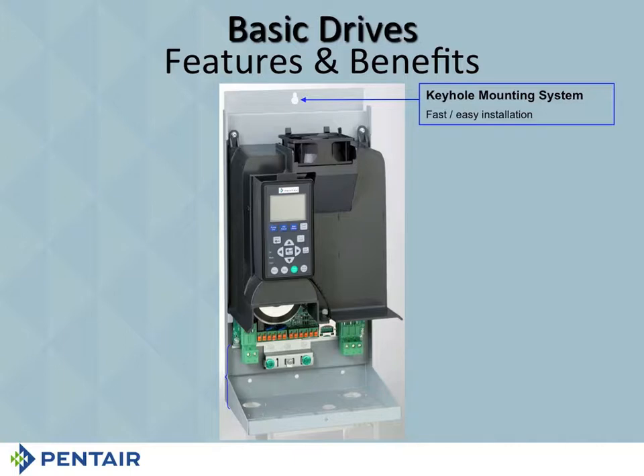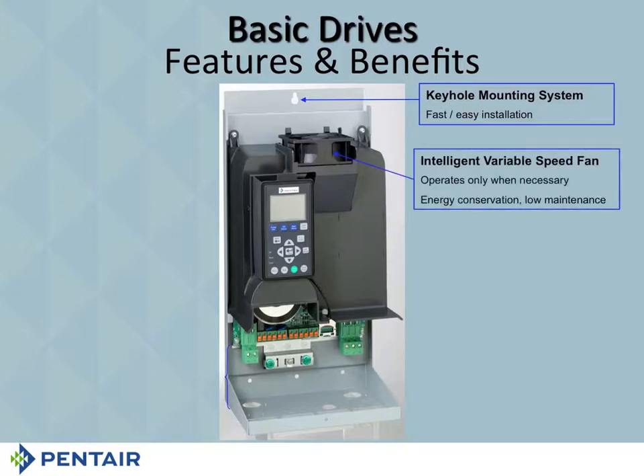All right? It does have an intelligent variable speed fan. It only operates, and this is what makes it intelligent, when it's necessary. There's a heat sink in the drive, and if it starts to get warm, it turns the fan on, which means depending on where you live, you may never hear that fan, okay? It may never, ever come on. Of course, it's going to conserve energy, and it means you minimize your maintenance a little bit.